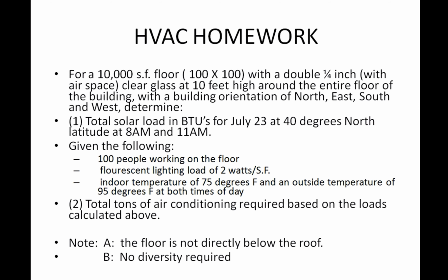What I'd like you to do is give me two answers. Number one, what's the total solar load in BTUs, given the condition that it's July 23rd at 40 degrees north latitude at two different times of day? And for each of those times of day, I'd like you to give me what the total tons of air conditioning required is based on those loads and these factors.